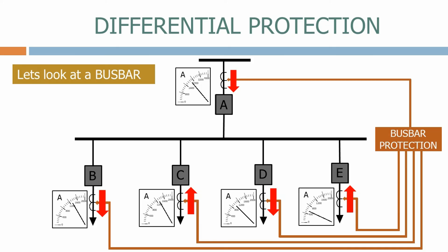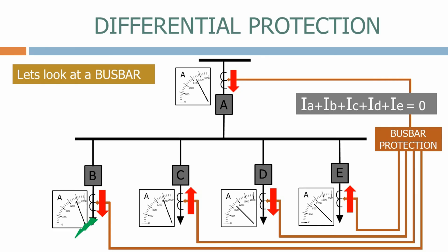Let's now apply a fault on one of the feeders. The current magnitude on the incomer will now increase substantially as it feeds the fault. If it's a fully connected system, the direction of the current on some feeders may also change as they back-feed power into the system, depending on the configuration of the network. Regardless of the direction and magnitude of these currents, the sum of the currents will still be zero and the busbar protection system will not operate. Let's now remove the fault.